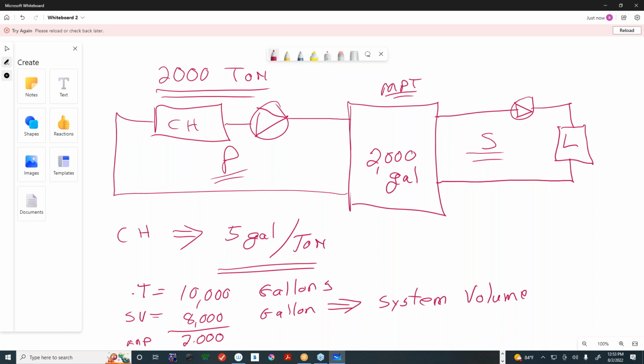Now, again, the important thing to keep in mind is that I picked a number that is commonly used in the industry, but it's not the only number. I always recommend you go back to the chiller manufacturer and get the actual gallons that the chiller manufacturer is looking for. And by the way, the same thing holds true for boilers. Boiler manufacturers are also looking for a minimum amount.